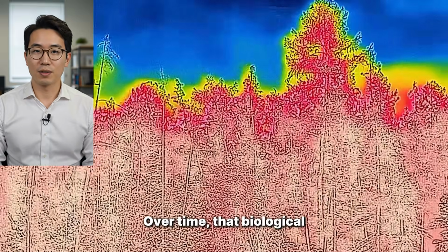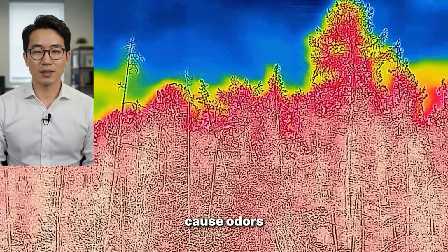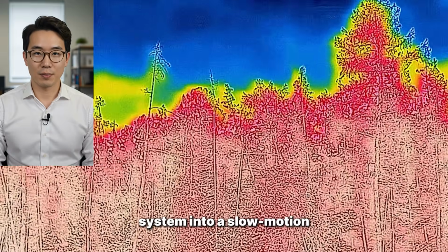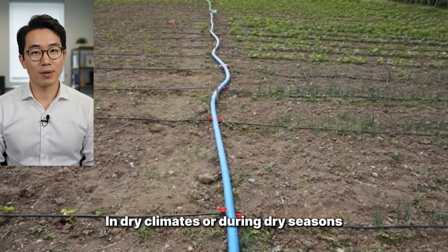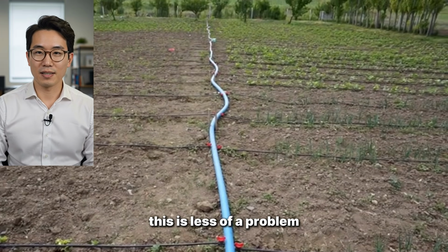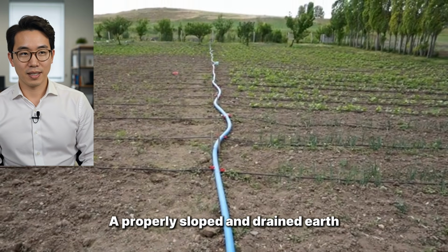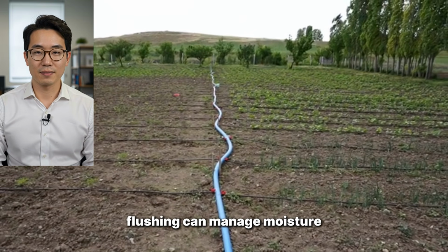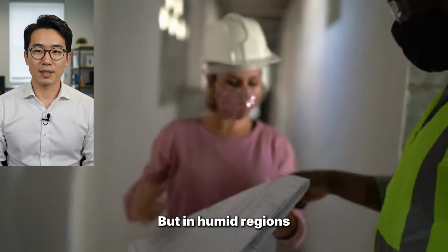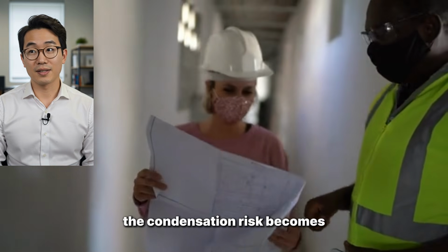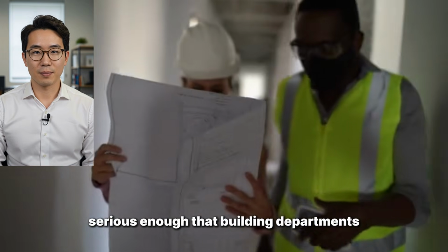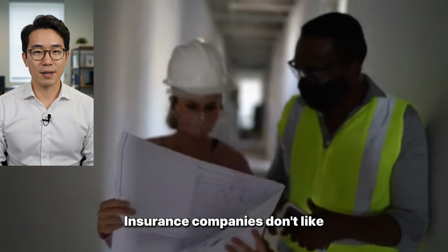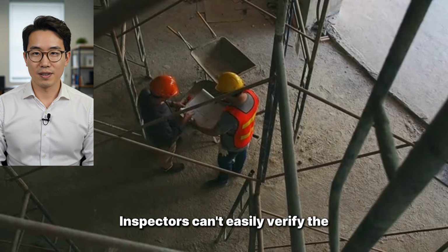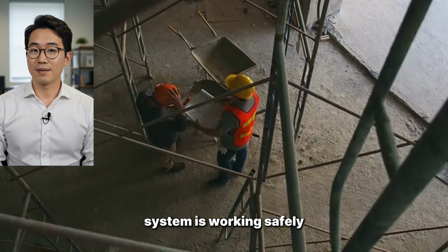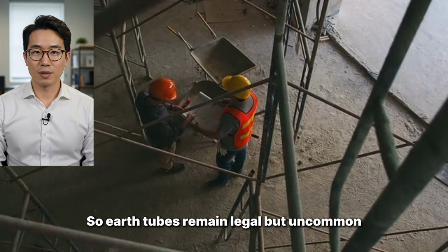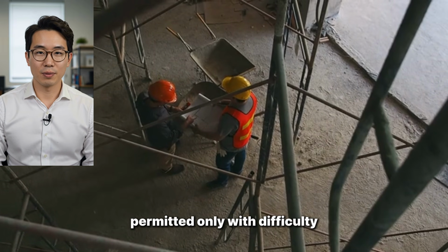Over time, that biological growth can degrade air quality, cause odors, and turn your passive cooling system into a slow-motion contamination risk. In dry climates, or during dry seasons, this is less of a problem. A properly sloped and drained earth tube with condensation collection and periodic flushing can manage moisture. But in humid regions, especially in summer, the condensation risk becomes serious enough that building departments hesitate to approve them. Insurance companies don't like unknown moisture paths. Inspectors can't easily verify the system is working safely. The liability is real, so earth tubes remain legal but uncommon, permitted only with difficulty.